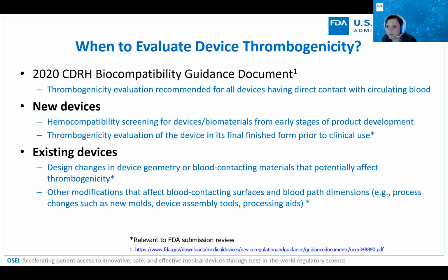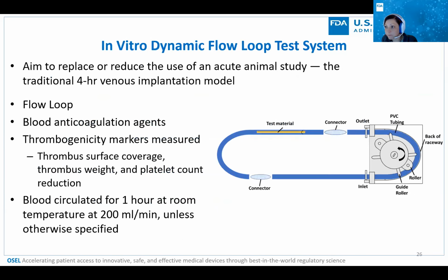Existing devices that have gone through the review process, if there's any design changes in device geometry or blood contacting materials, that could potentially affect thrombogenicity and would have to be evaluated. And then also any other modifications that affect blood contacting surfaces or blood path dimensions. This can be like new molds that are used, device assembly tools, or processing aids. All of these recommendations can be found in this biocompatibility guidance document for your reference at a later date, if that is relevant for your particular medical product.